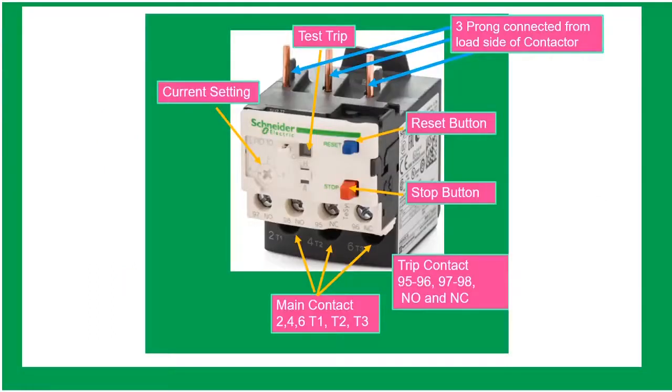The overload relay is always part of magnetic contactor and is designed to protect the motor against prolonged overcurrent. This means if the motor is running for too long with high current, it will overheat and destroy the motor. One of the causes for this is bad bearing.